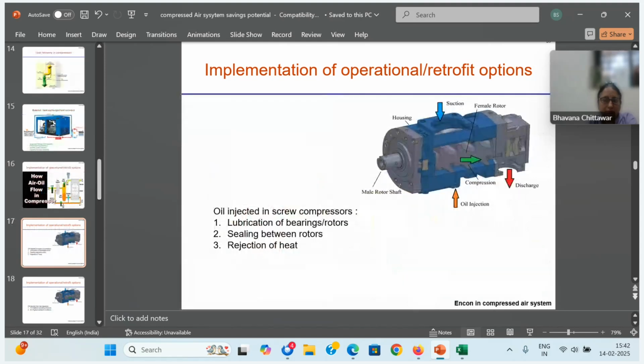So how the male and female rotors work, and how oil is injected. The purpose of oil injection, as I already told, is lubrication, sealing between rotors, and rejection of heat. So here we can check the rejection of heat. The temperature should not rise after putting the restrictor. That we have to monitor. If temperature is not rising, if power is not rising, you can go ahead. You can record the savings. Even 1% savings is a good amount.